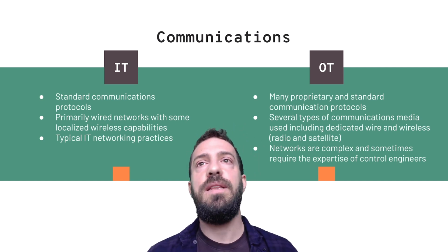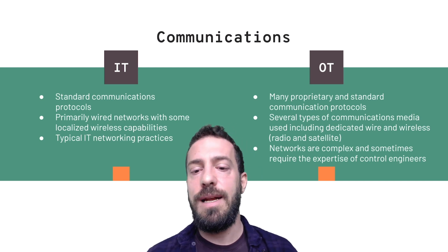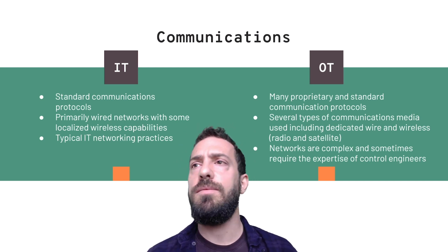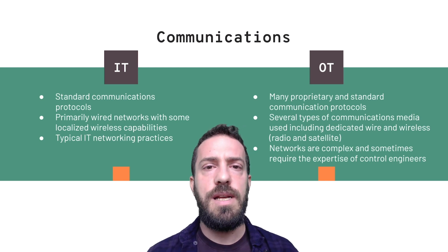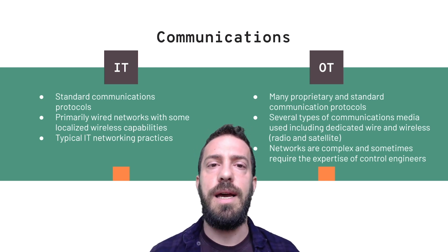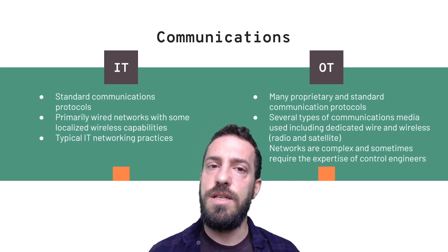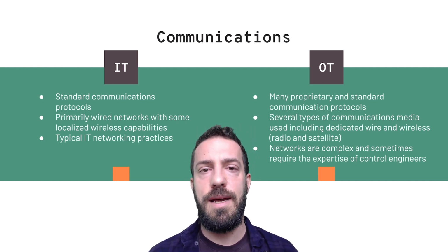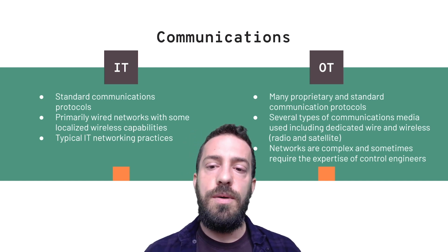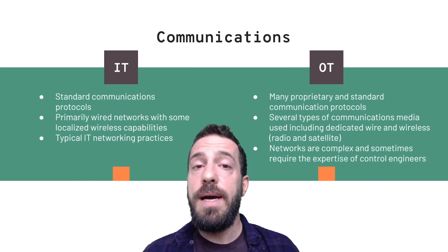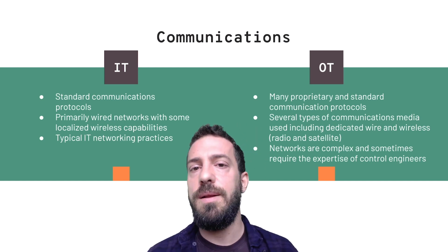Proprietary is a problem. Different communication media is a problem because we have to think of potential attacks on each side, right? We've seen attacks through radio frequency because that's something everybody can do, everybody can send radio signals, right? So if you do radio frequency communication, you have to ensure that there's no jamming or there's no man-in-the-middle attacks that can be performed by adversaries. So in the OT side, deep packet inspection on Modbus may not be straightforward, or on DNP3.